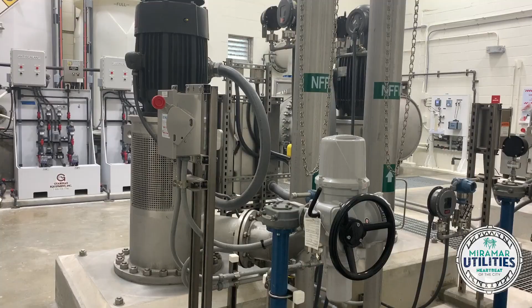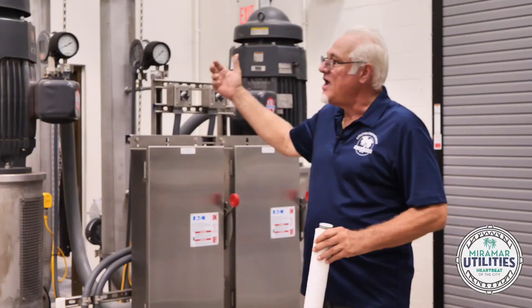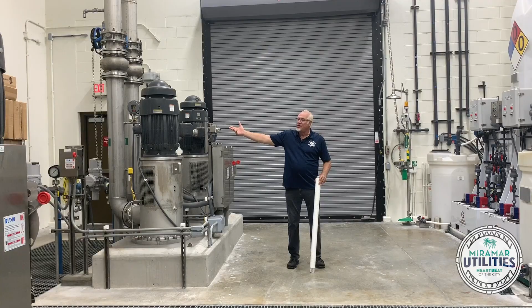After the injection of antiscalant and fluoride in the cartridge filters, the water flows to these 75 horsepower feed motors. Each one raises the pressure up to about 100 psi to feed our nanofiltration units. We have 4 treatment units, each producing 1.5 million gallons a day, and each pump can pump 1.5 million gallons a day to it. That's a lot of water - perfect for supplying the ever-growing city of Miramar.